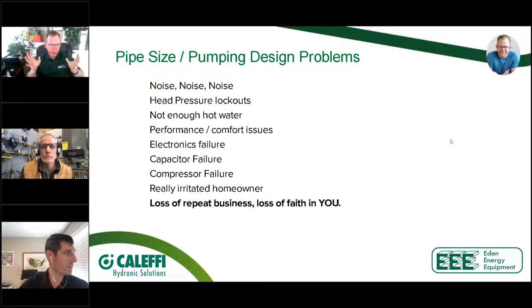So as we talk about this, I'm just going to share some symptoms because it's worth everybody knowing. If I don't pipe a heat pump properly, if I don't work off a design and do it properly, the number one thing that you're going to experience is noise. You're going to know immediately. As soon as you start that unit up, you're like, huh, is it supposed to sound like that? And what's great for me is if a technician calls me or if I'm collaborating on something, I can tell when they call me whether that heat pump's set up right, because I can hear it.